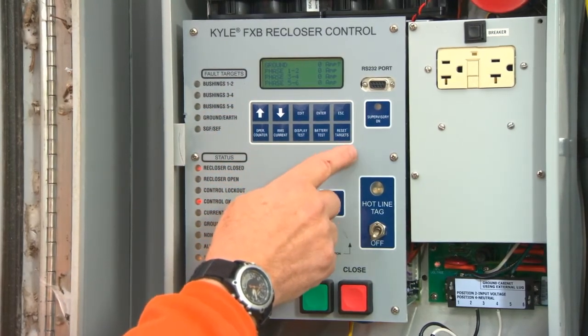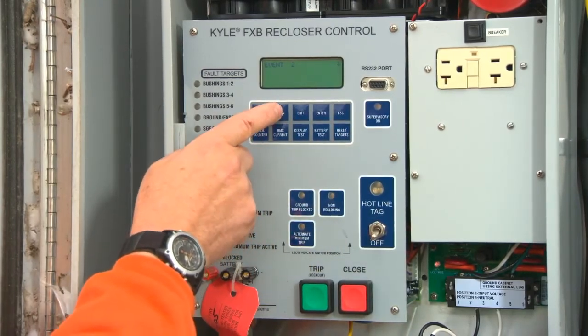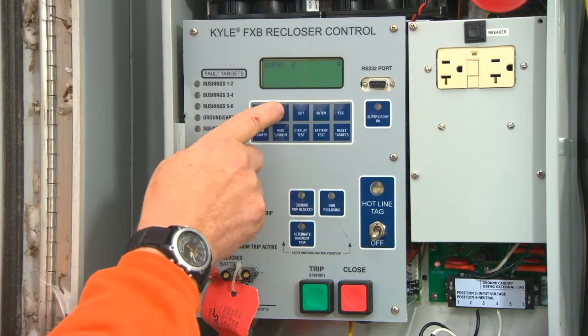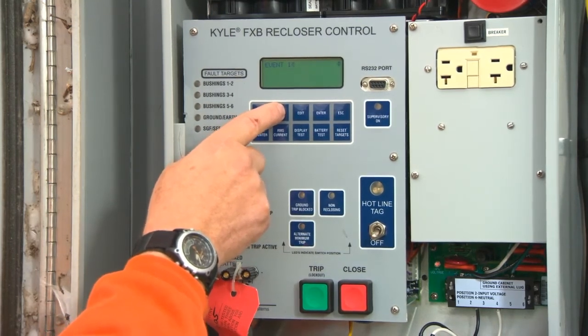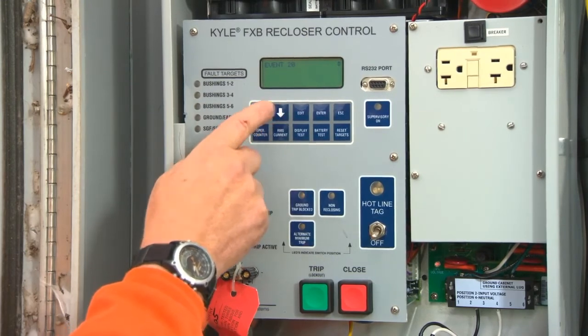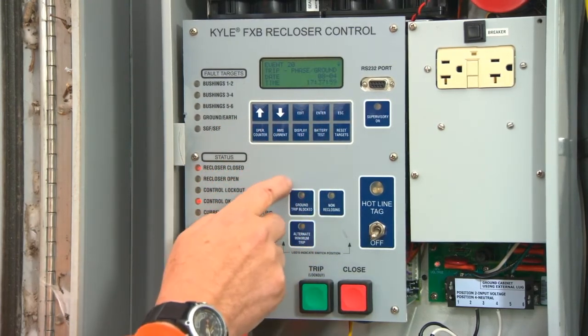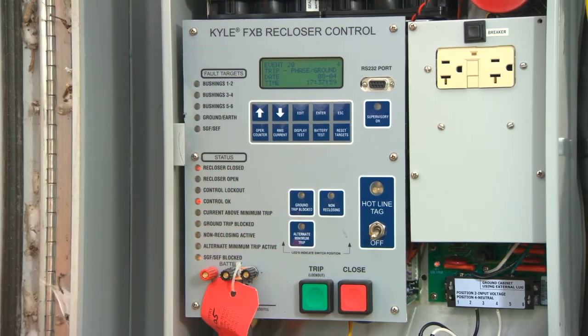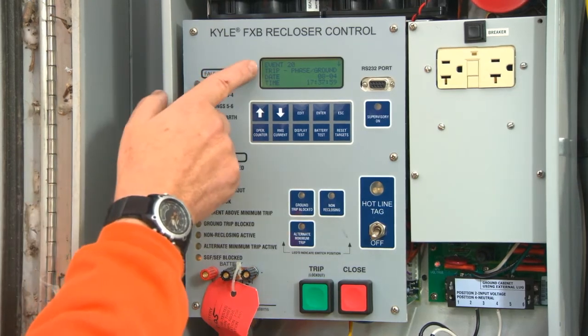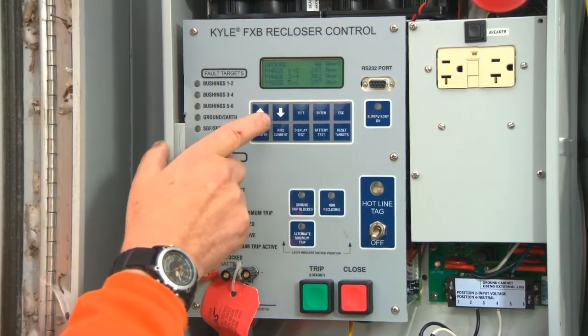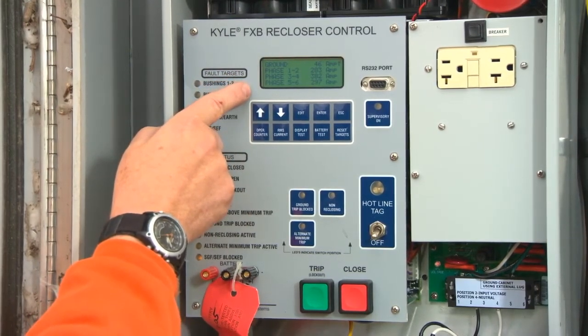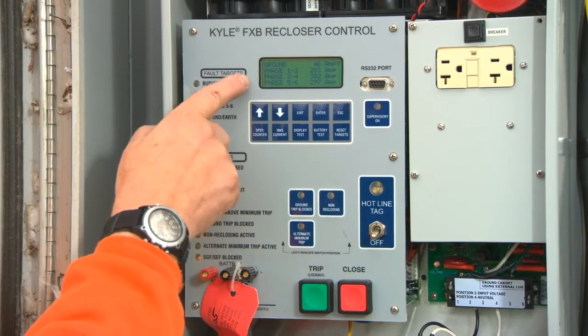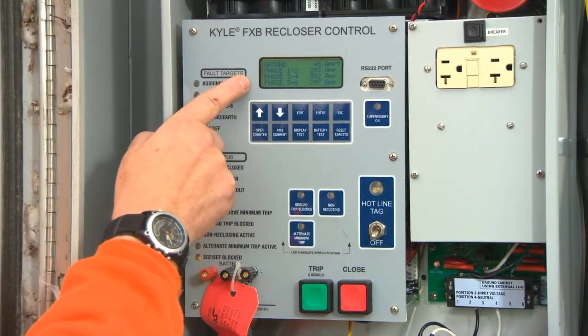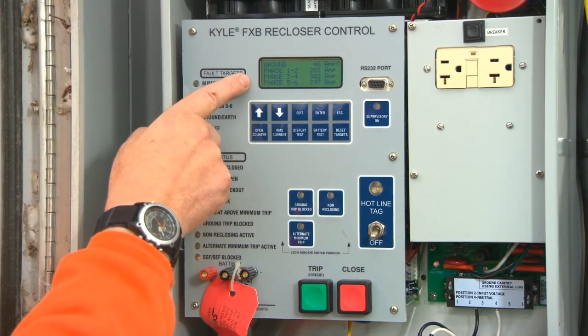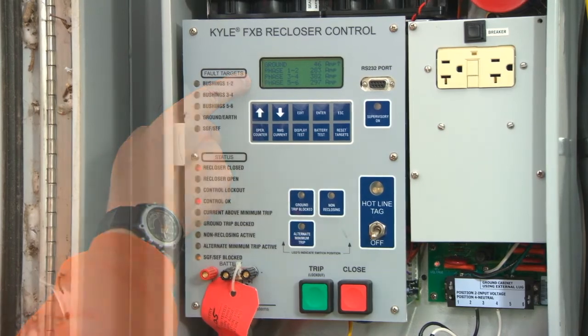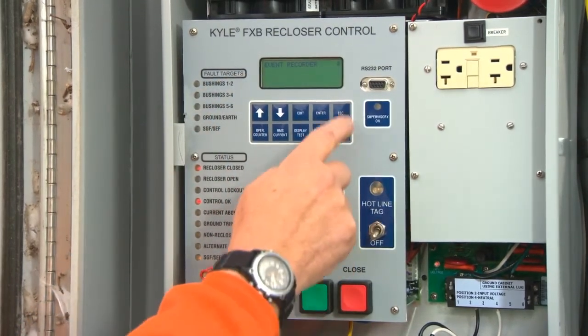Use the Escape key to back out and find an event. Using the down arrow to drop down to Event 20, press Enter. The screen will now display the event, in this case a trip from phase to ground. The date and time are also displayed. Press down again to display the amperage on each phase, along with the actual faulted phase. In this application, the display shows that the phase 3 to 4 center bushing tripped out at 382 amps. These units are set to trip at 350 amps. Pressing Escape 3 times will return you to the main display screen.